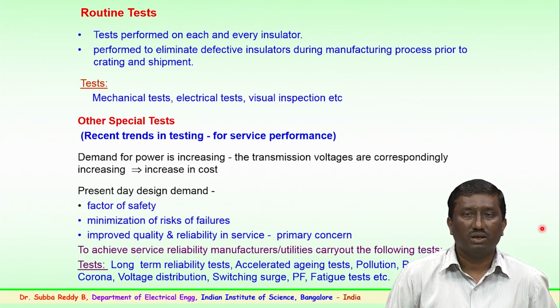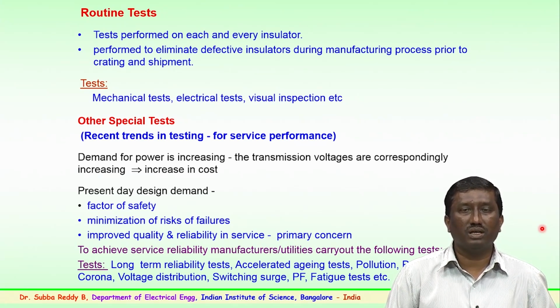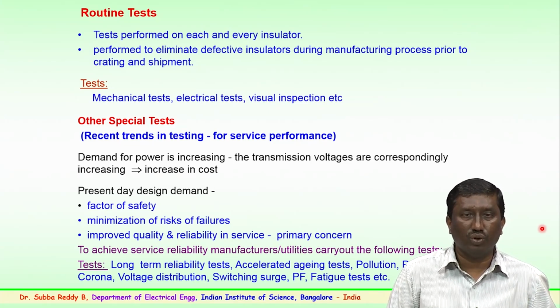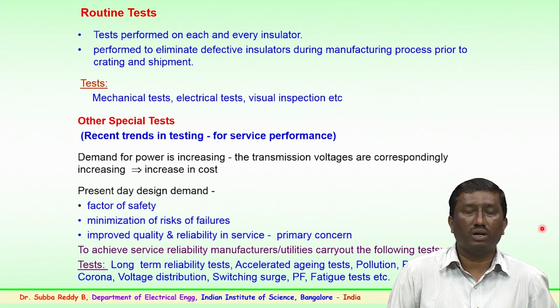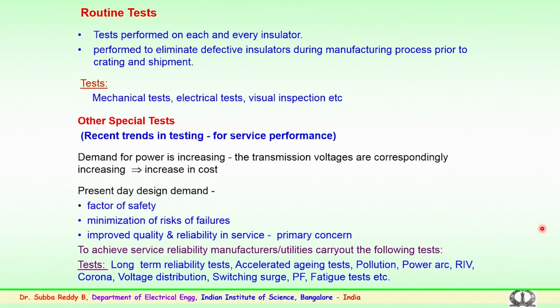This increases the cost of the insulator string, the tower and many other things. So the present day design demands a factor of safety, which is very important. Minimization of the risk of failures has to be kept in mind, and improved quality and reliability in service is a primary concern at higher voltages, extra high voltage or ultra high voltage. To achieve service reliability, manufacturers or utilities normally conduct the following tests, categorized as special tests, particularly for EHV or ultra high voltage levels.